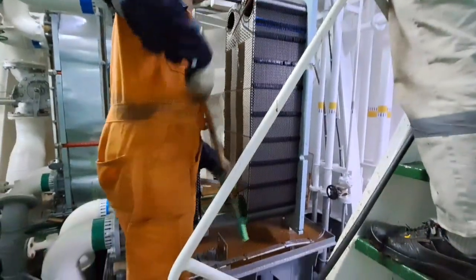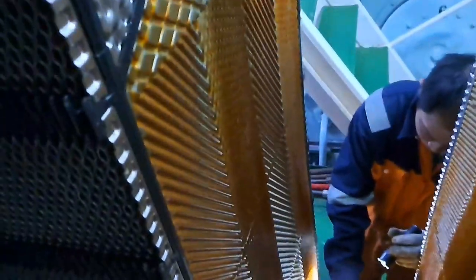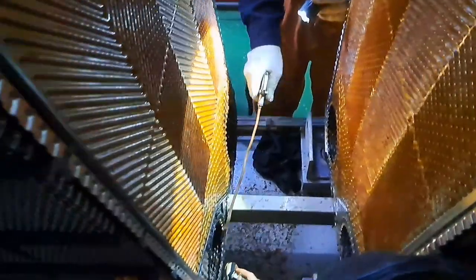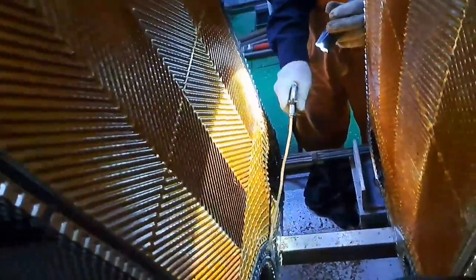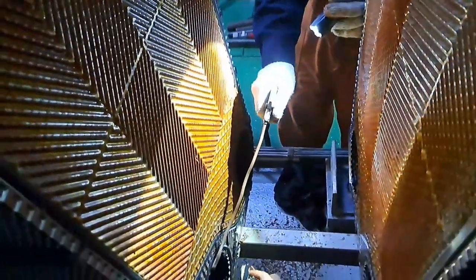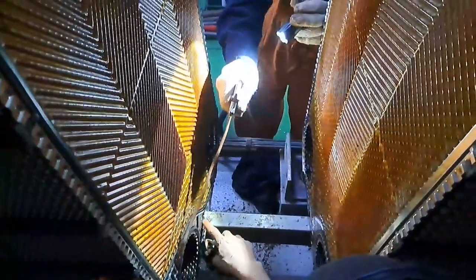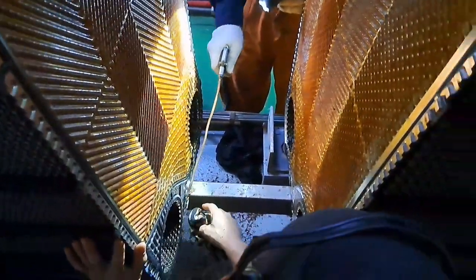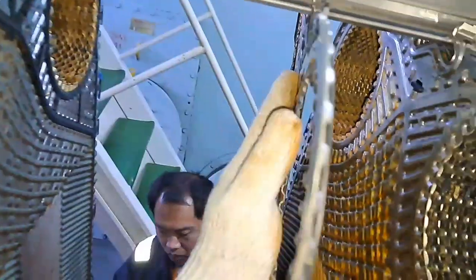And you have a loss of two plates, take them out, and there is little influence on the performance. However, with the two plates removed, be sure you know how much to tighten the plate heat exchanger. Okay, this information should be in your manual or available from the manufacturer.